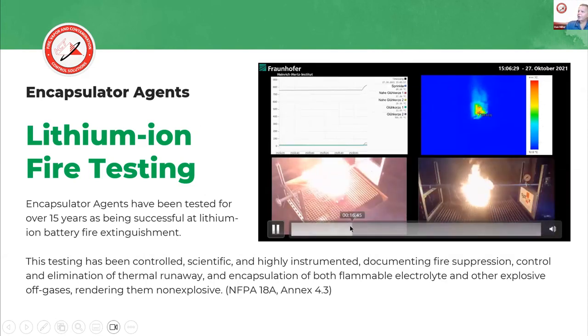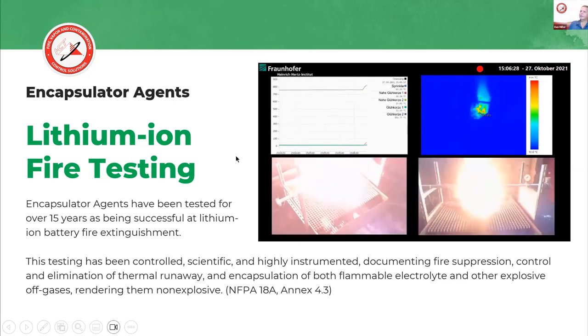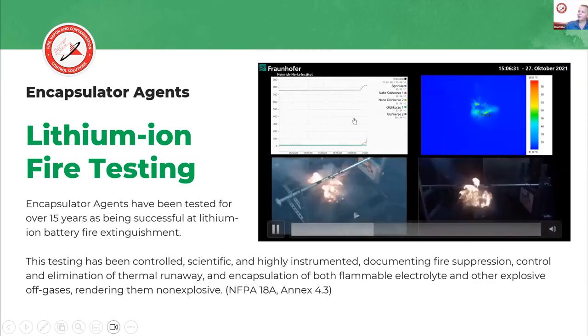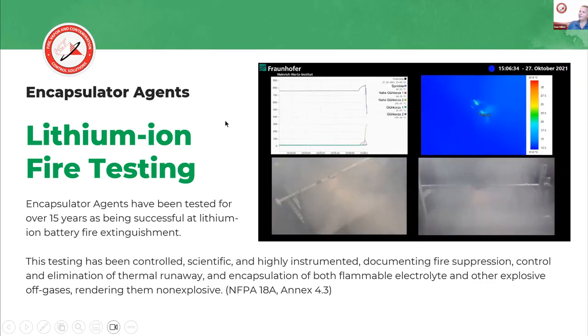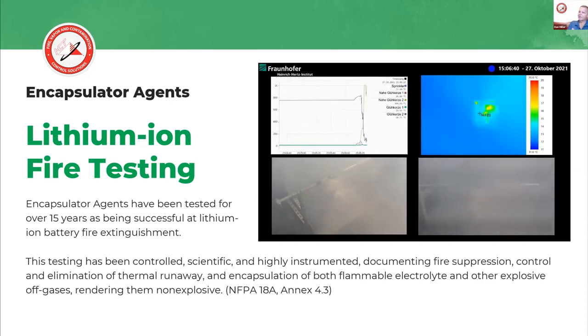What you're going to see in this video is thermal runaway beginning. You're going to see the thermal indicators up on your upper left from the thermocouples climb in temperature. The F500 goes onto the batteries. The temperature drops immediately. The fire goes out and then stays out. That same pattern occurs over and over and over again. And in really all of our tests, once the F500 is allowed to interface with the cells and the electrolytes, the fire goes out and it does stay out. The temperature never rises again.